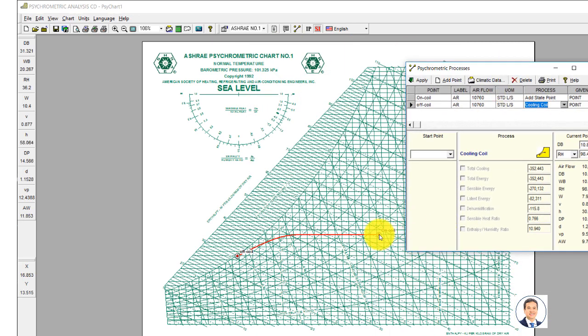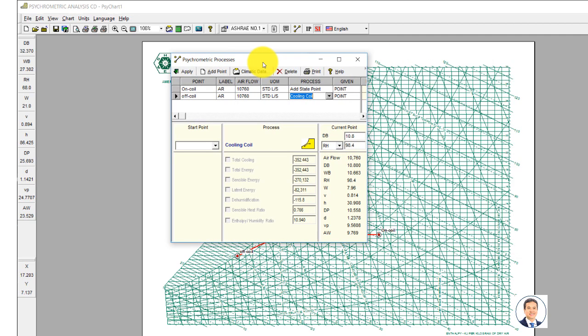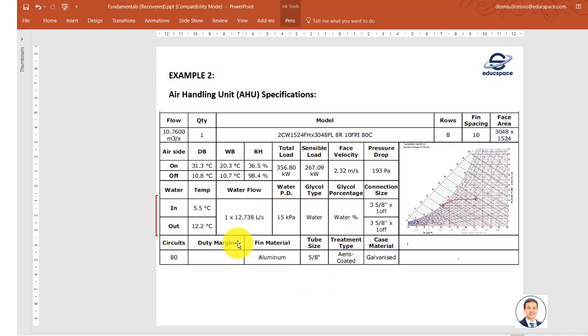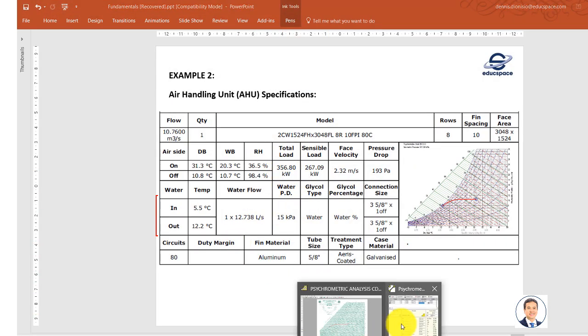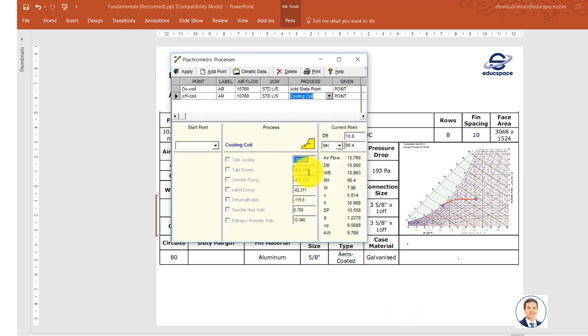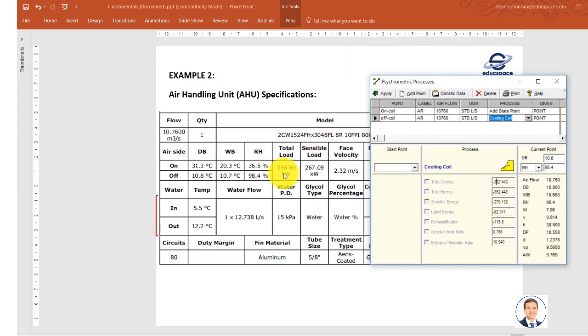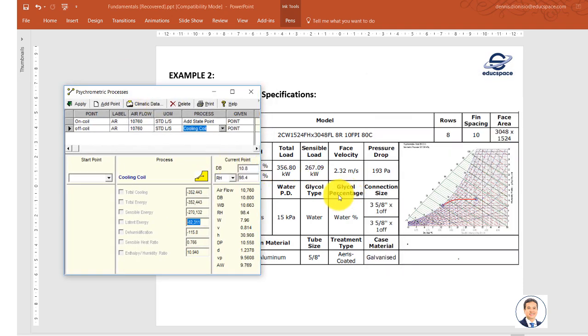Notice this is the on-coil condition and this is the off-coil condition. So what's listed in the spec is 356. Tama, 356. And what we got is 352 - a small difference, alright, just a small difference. That's in terms of kilowatts, and kilowatt means kilojoule per second. The total heat here is 352, and sensible is 267 here, versus 270 - so that's also close. This one is the energy in terms of watt per hour, and that's basically the latent heat capacity.